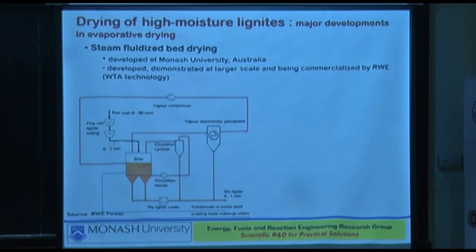These are the hoppers which go into the dryer, and inside the dryer, drying heat is provided through inbuilt, immersed tubes, through which goes the steam. The steam condenses into good quality water, and that can go to the condensate as to the power plant, so it's not lost except the ones which are lost in drift. But the water that is released from the dryer, from the coal, comes out in the form of vapor, water vapor, so it's gas, it's not condensate.